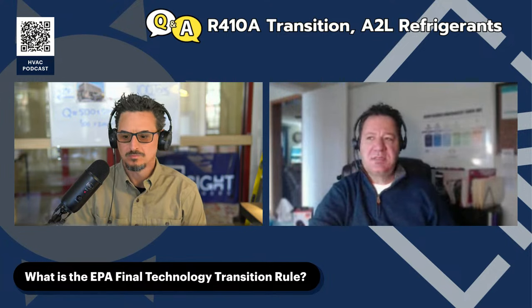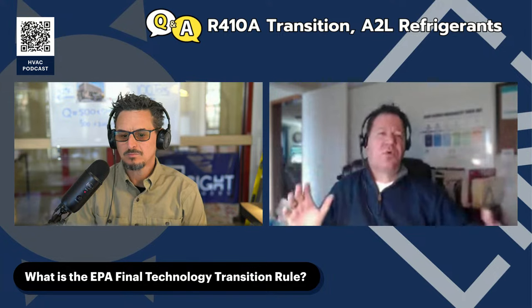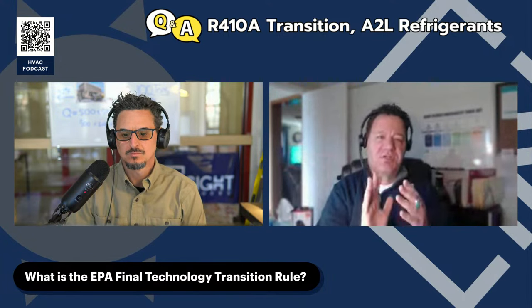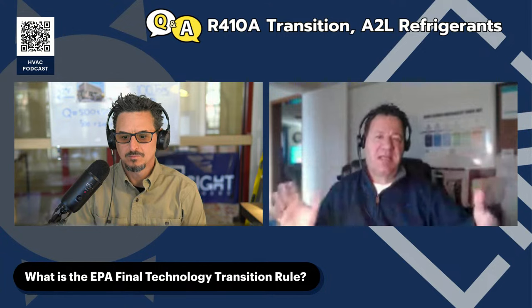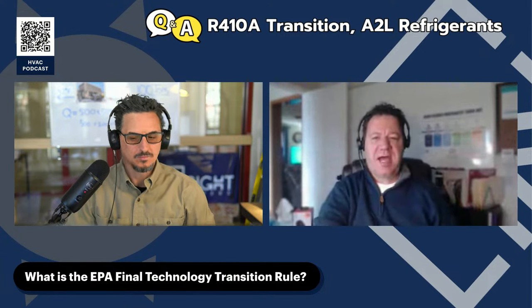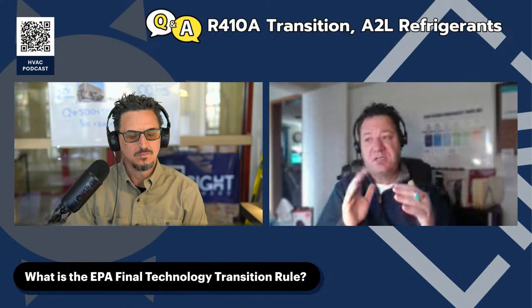The way I like to think of it, since I used to teach supermarkets and larger classes on the commercial refrigeration side prior to coming here at Copeland, is the longer the line set, the more opportunity for leaks, and the smaller window you'll have for refrigerants as far as GWP. So that's a good part of the application type thing. The smaller that line set gets, the higher the GWP gets.